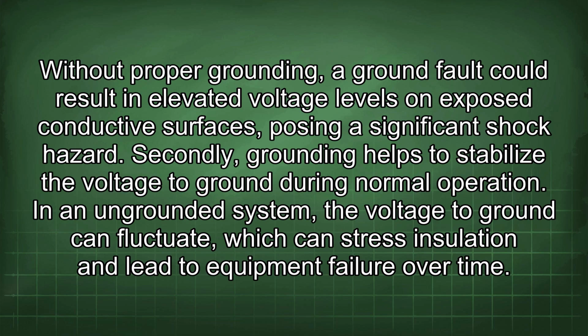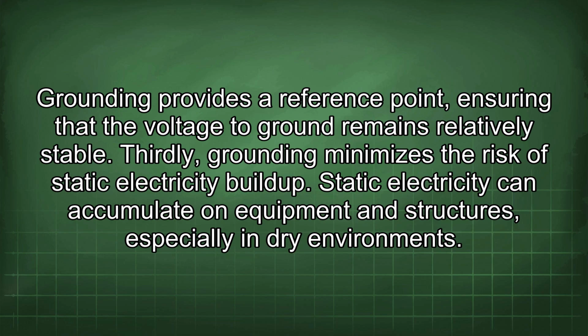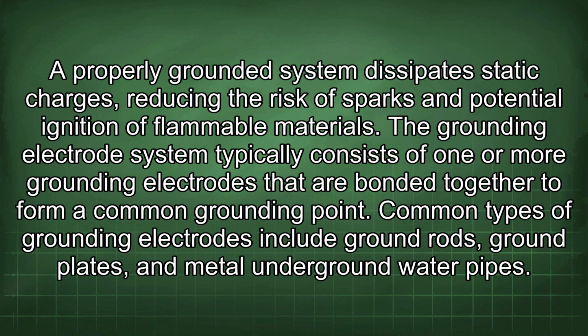In an ungrounded system, the voltage to ground can fluctuate, which can stress insulation and lead to equipment failure over time. Grounding provides a reference point, ensuring that the voltage to ground remains relatively stable. Thirdly, grounding minimizes the risk of static electricity buildup. Static electricity can accumulate on equipment and structures, especially in dry environments. A properly grounded system dissipates static charges, reducing the risk of sparks and potential ignition of flammable materials.